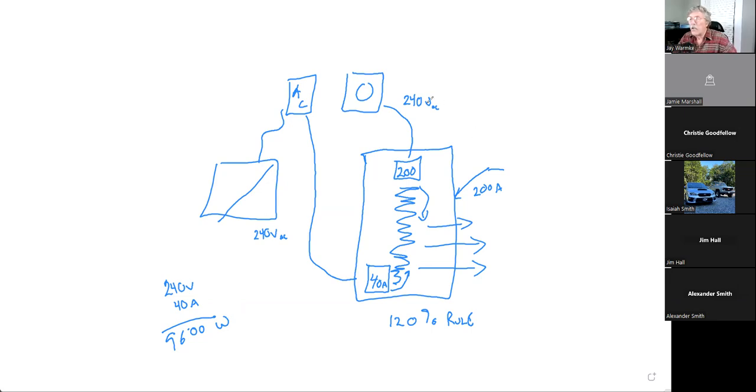All right, so 9,600. So you would be tempted to say, okay, the inverter could have an output of 9,600 watts or a 9.6 kW inverter. But you would be wrong because all of our wires and all of our breakers have to have that 1.25 NEC safety measure. So you don't want to size your things right up to the limit.